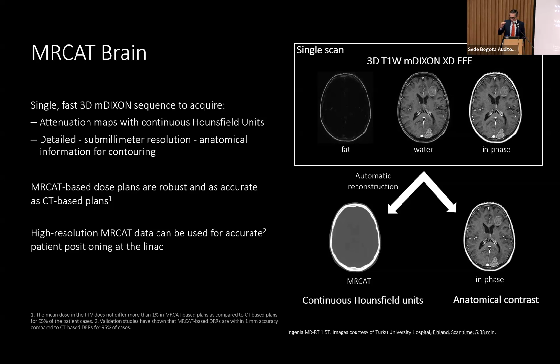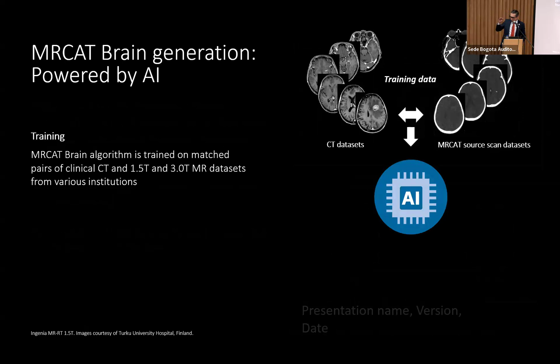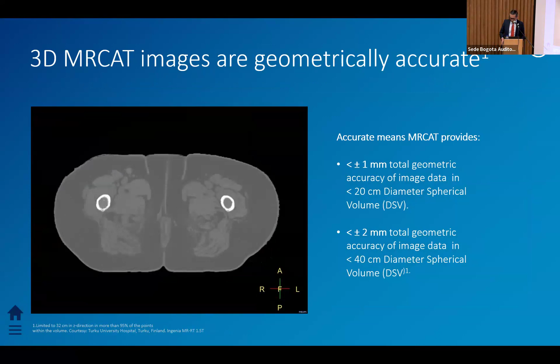Why? Because we have references of different tissues, as you use in CT, because with CT, you have to use a water phantom to have the center of the Hounsfield units, that is water. In this case, we have similar phantoms for these purposes. And of course, they use artificial intelligence as well in order to have a better depiction. This kind of image that we are showing is a CT image that was generated using an MR. Just keep in mind the geometrical accuracy, less than 1 millimeter, and less than 2 millimeters for all the sets in different axes.